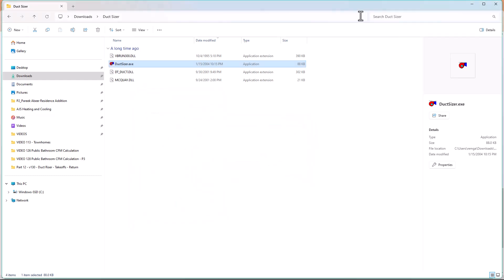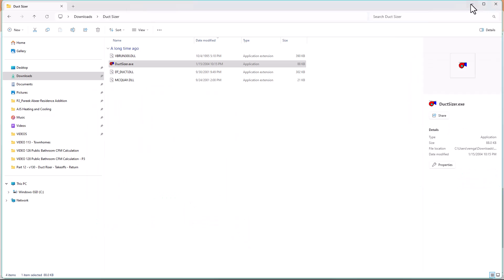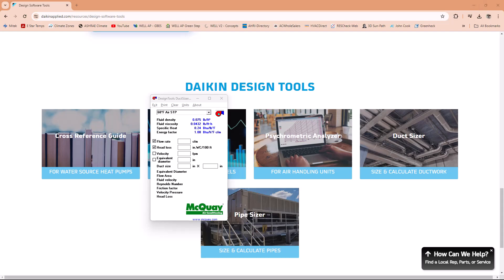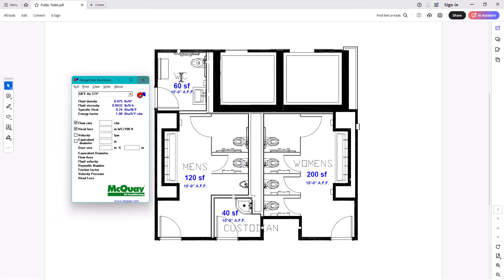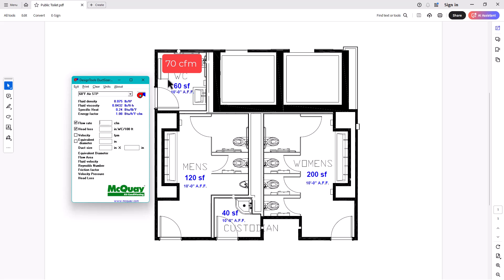Alrighty. So now what we're gonna do is I'm just gonna keep this open and I'm just gonna show you a very quick example how this works, because we're gonna be using this a lot or you can always use your DuctSizer calculator. I mean your ductulator. Alright. So in here, what do we have? For example, you have in here from my previous video for these, for this toilet, imagine that you need 70 CFM depending on the code. You need 70 CFM in here. What is your duct size? What is it? You need 70 CFM.